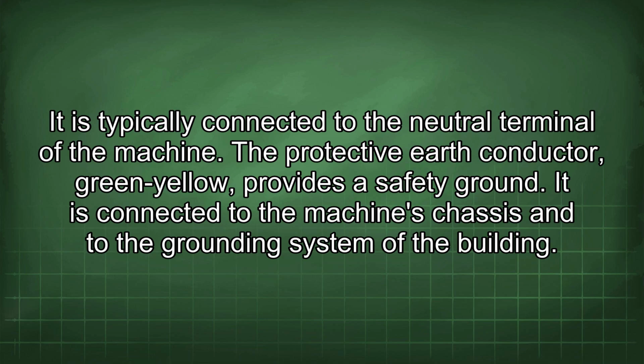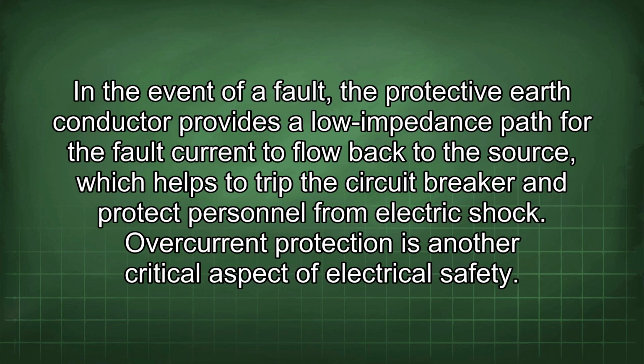The protective earth conductor, green-yellow, provides a safety ground. It is connected to the machine's chassis and to the grounding system of the building. In the event of a fault, the protective earth conductor provides a low impedance path for the fault current to flow back to the source, which helps to trip the circuit breaker and protect personnel from electric shock.